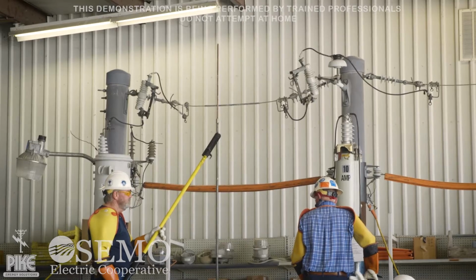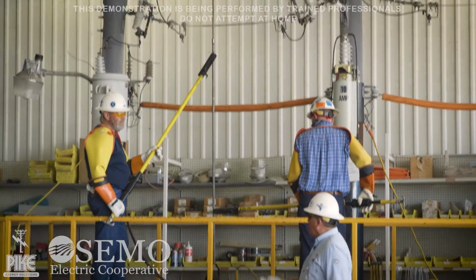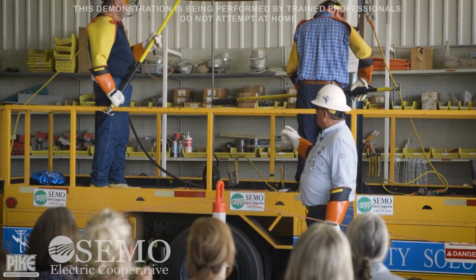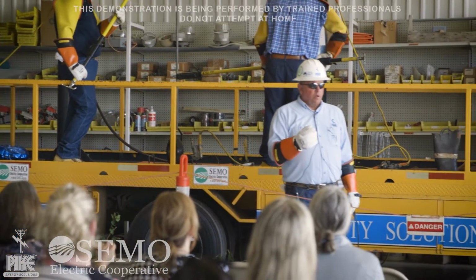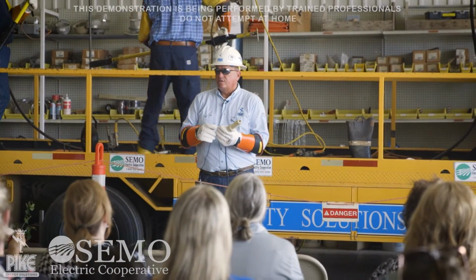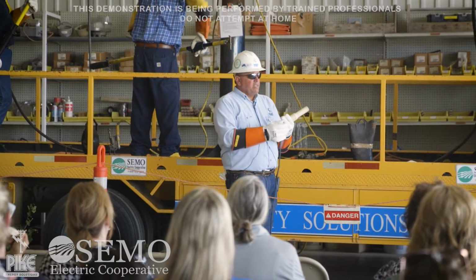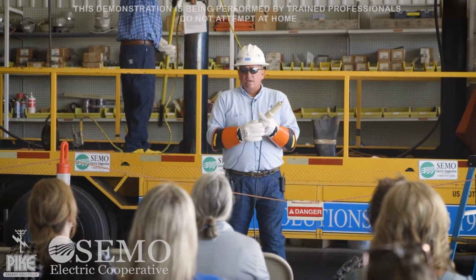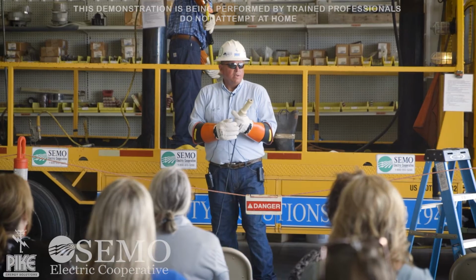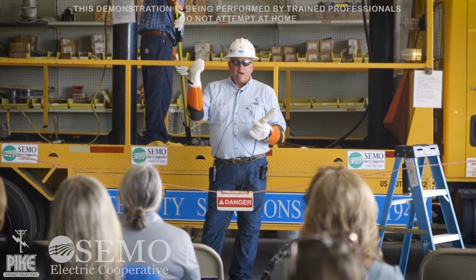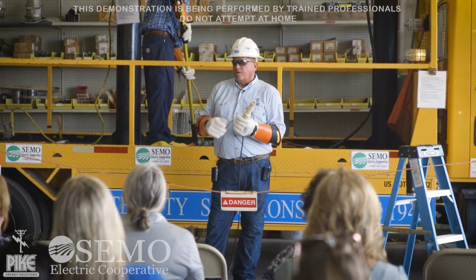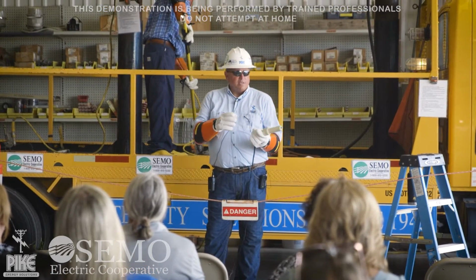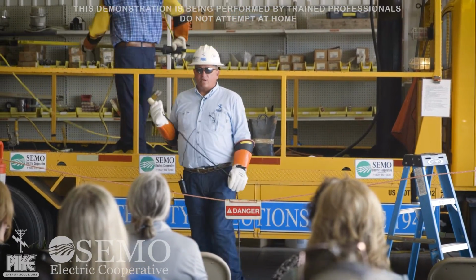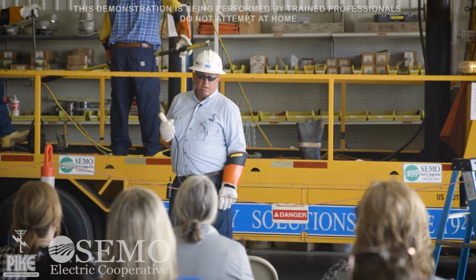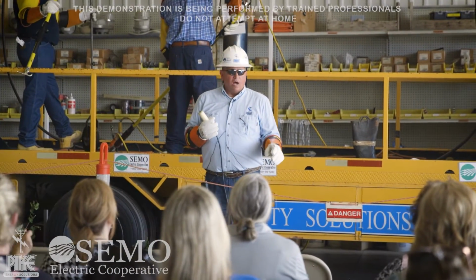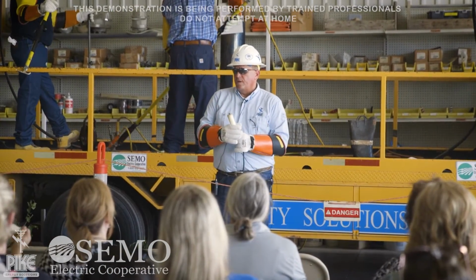So you've seen the fire at the top, you've seen the fire at the bottom. One thing we do at Pike, we're going to ground it. We ground our mobile equipment such as pullers, tensioners, line trucks, digger derricks, mobile cranes, anything that has a metal part that has a continuity back from the tip down to the ground. We ground that for protection of the employees, not for protection of the equipment, but for protection of the employees.